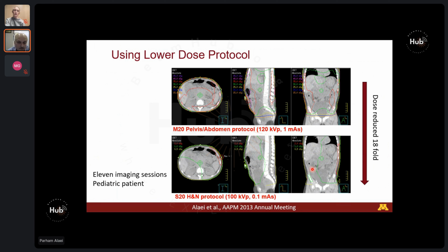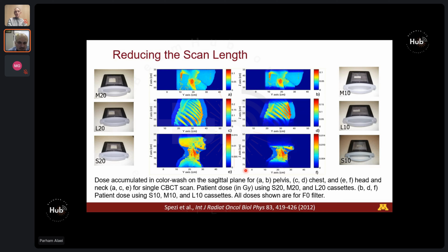Another one is a simulated study. Again, this shows the scan length craniocaudally in head to toe. These are the Elekta cassettes, obviously, M, L, and S20. And 20, as you know, is basically going in the craniocaudal direction. And if you use the 10 cassettes, you cut down on the extent of the image volume. So you can lower the image volume if warranted, and if your target is such that you can adequately see your PTV and your organs at risk, you can actually do that, switch from that to that.